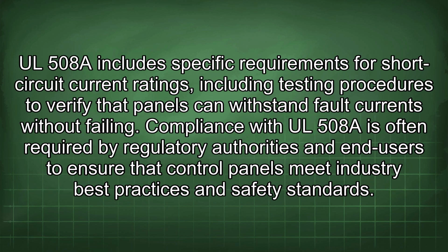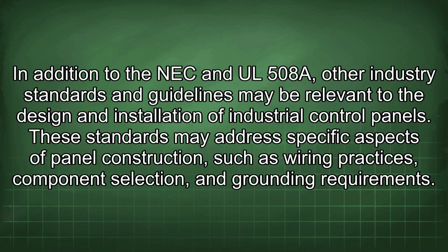UL 508 includes specific requirements for short-circuit current ratings, including testing procedures to verify that panels can withstand fault currents without failing. Compliance with UL 508 is often required by regulatory authorities and end users to ensure that control panels meet industry best practices and safety standards. In addition to the NEC and UL 508A, other industry standards and guidelines may be relevant to the design and installation of industrial control panels.